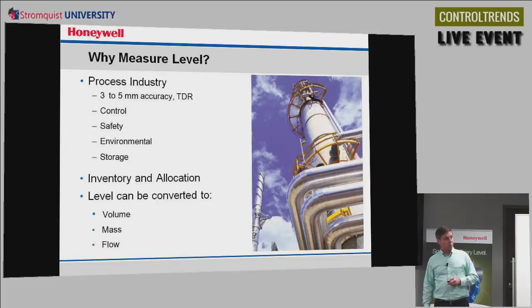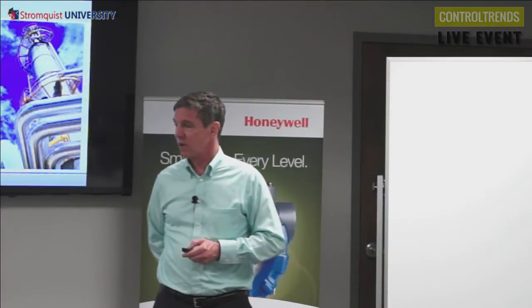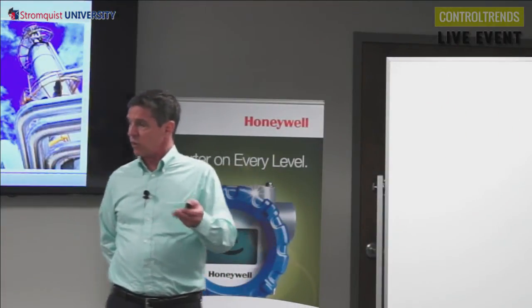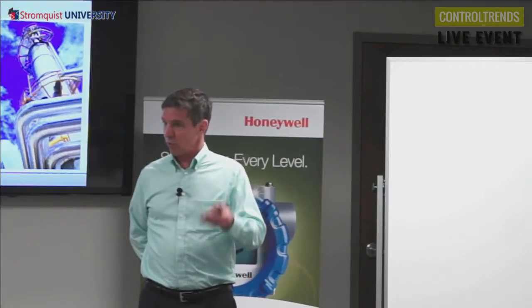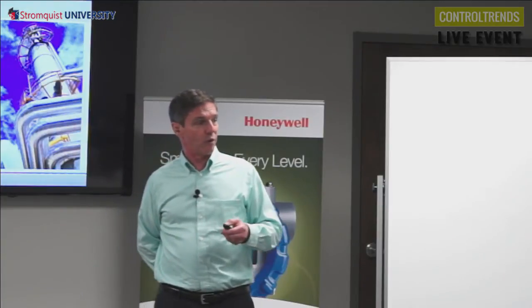So allocation means really keeping track of what product is in what unit and transfers and so forth. So it's important to be accurate, but it doesn't need to be quite as accurate as, say, the inventory tank gauging. And level, if we know the level within a tank, if we know the shape of the tank, we can convert that into volume. And if you know the density of the material that's in there, you can convert that volume into mass. And finally, you can use level to determine flow, if you know the amount of time it takes to move a certain volume.